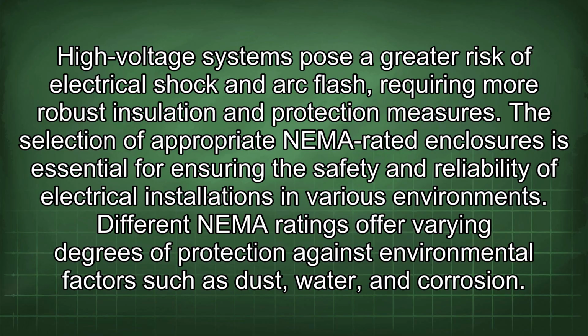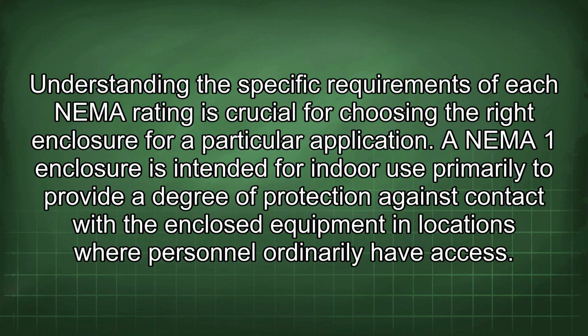The selection of appropriate NEMA-rated enclosures is essential for ensuring the safety and reliability of electrical installations in various environments. Different NEMA ratings offer varying degrees of protection against environmental factors such as dust, water, and corrosion. Understanding the specific requirements of each NEMA rating is crucial for choosing the right enclosure for a particular application. A NEMA 1 enclosure is intended for indoor use primarily to provide a degree of protection against contact with the enclosed equipment in locations where personnel ordinarily have access.